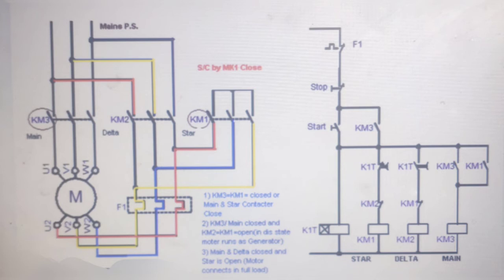We have to take three outputs from the delta contactor to motor U1, V1, W1. Then the same R will be given to KM2, that is delta contactor, then we have to take output. That R goes straight to V2 of the motor and Y goes to W2 of the motor.